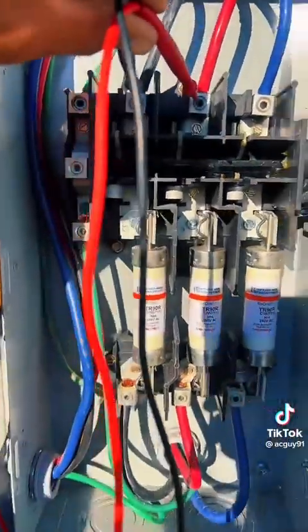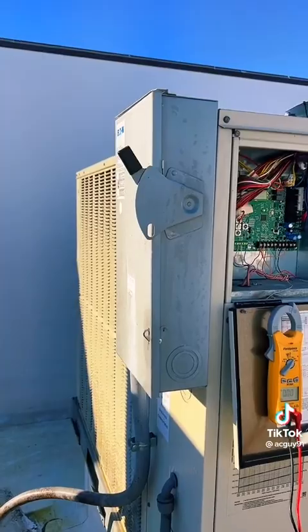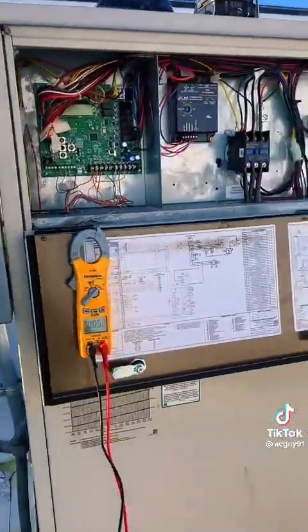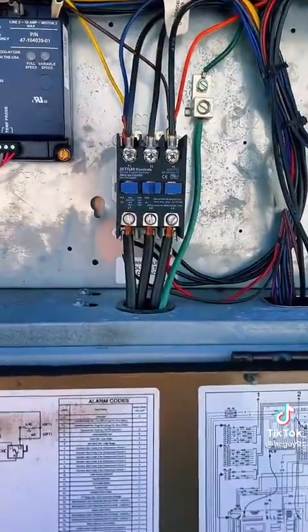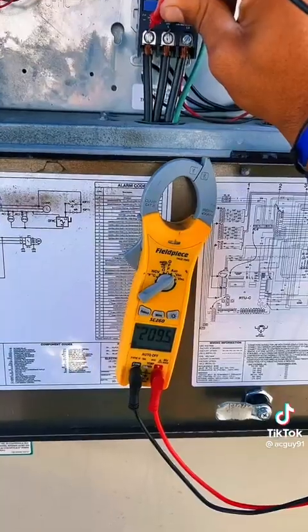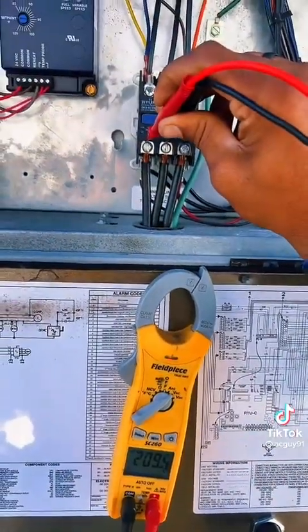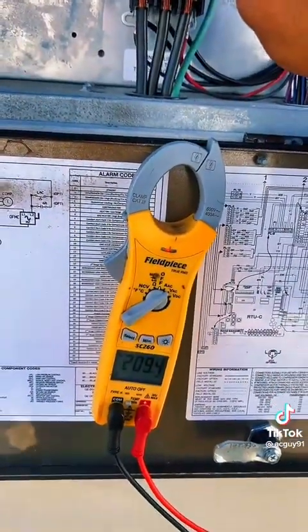So now let's go a little further. All right, so from my disconnect, power immediately comes in, goes right into this contactor. So right now we're breaking this thing down in steps. I went to the disconnect, I saw I had power in, I turned the disconnect off. Now I want to see if my power out is making it to my contactor. Jesus, look at me. And yes, my voltage is making it from my disconnect to my contactor. So now let's keep moving.